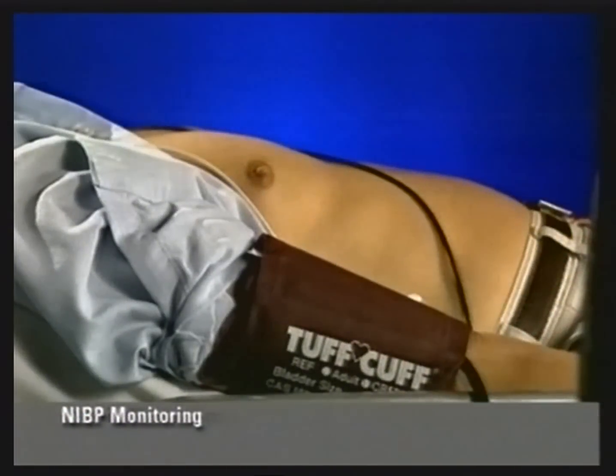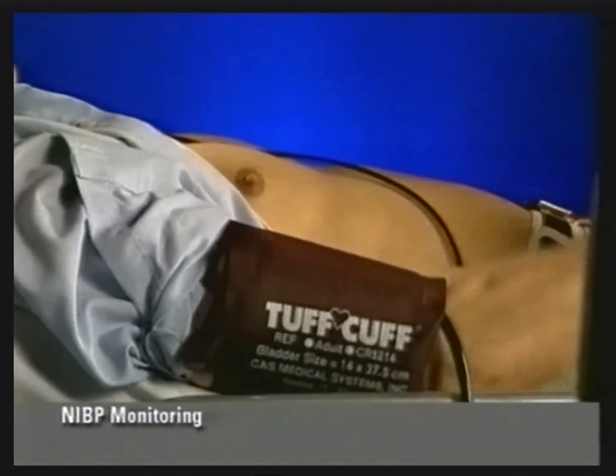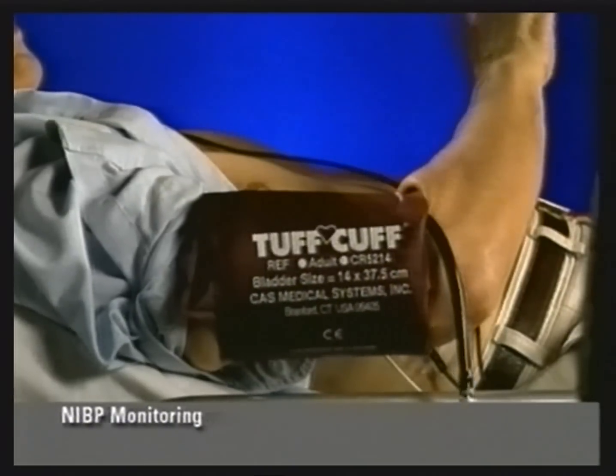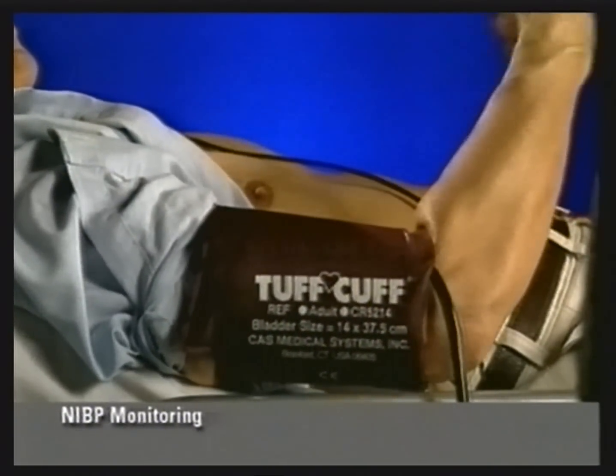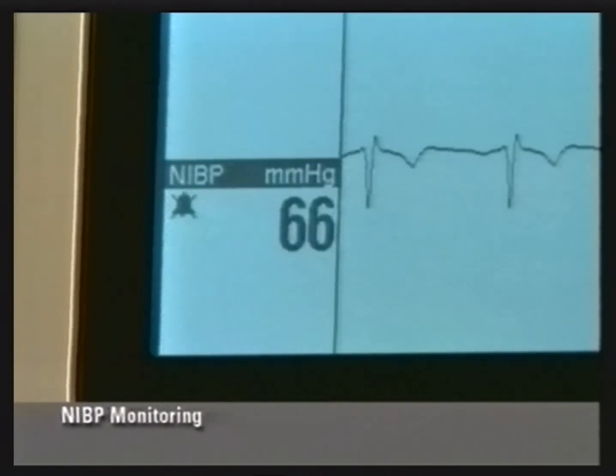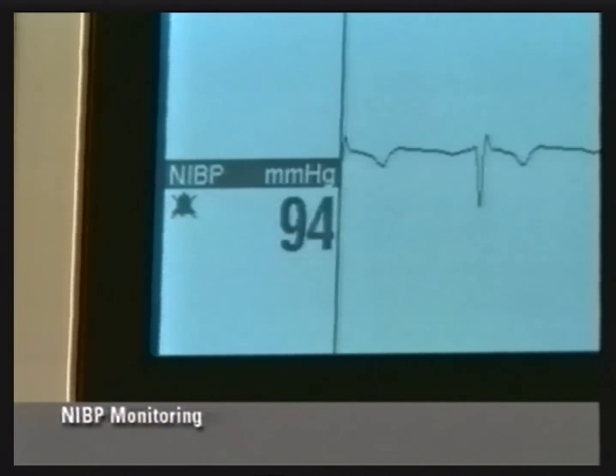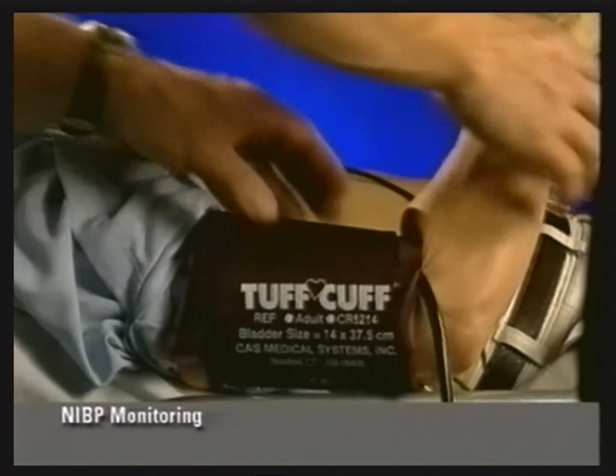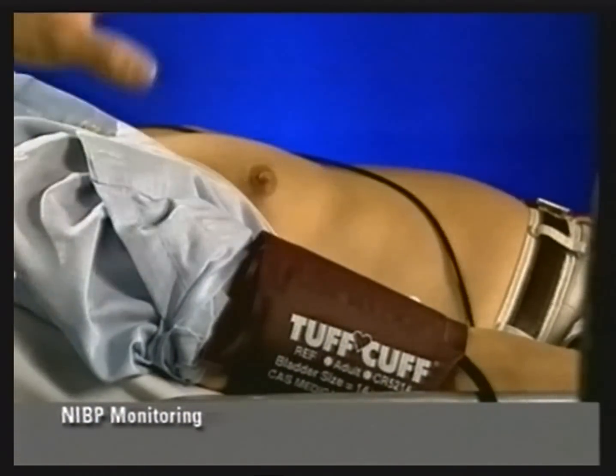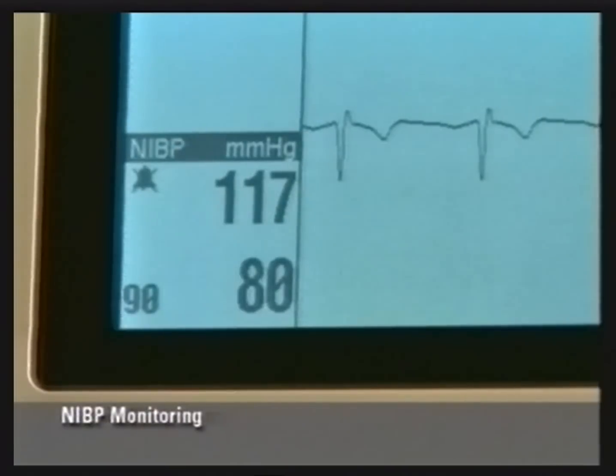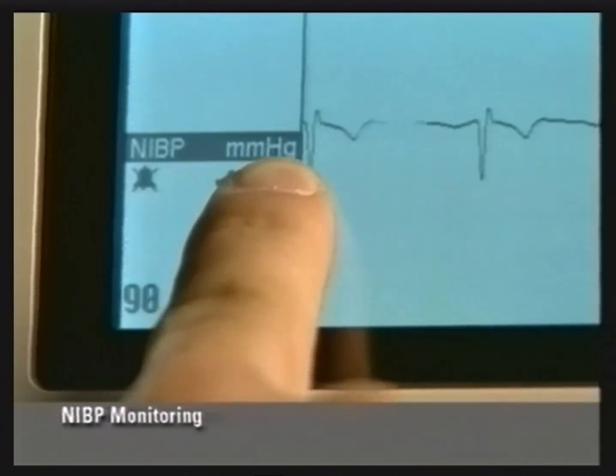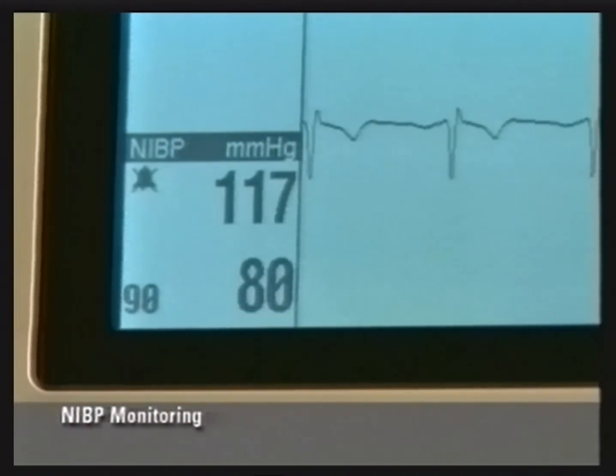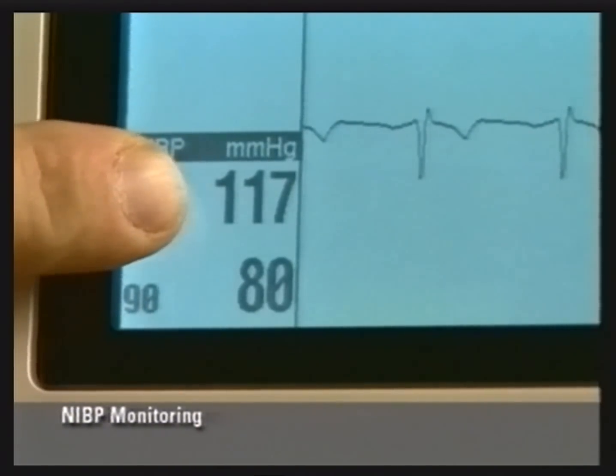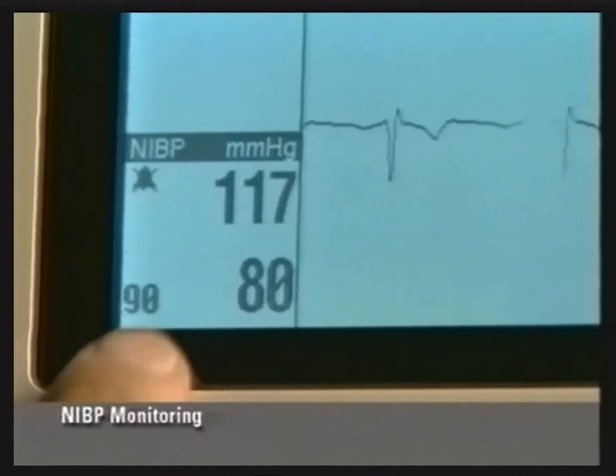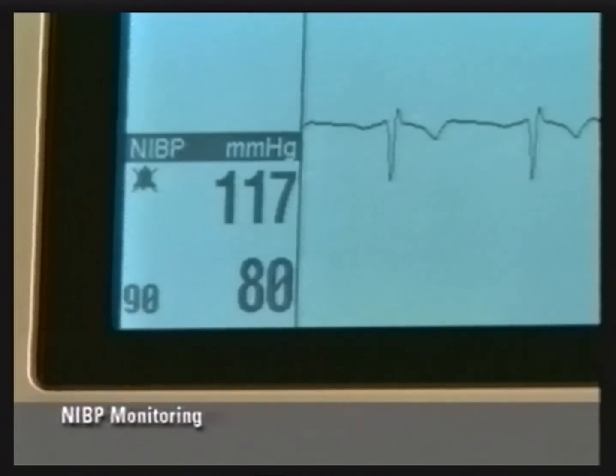Be sure the patient's arm is not moving during the deflation cycle. Arm movement will interfere with the measurement and cause the NIBP monitor to reinflate and take longer to obtain a reading. This can become very uncomfortable for the patient. The blood pressure is shown here in millimeters of mercury. Blood pressure may also be configured for measurement in kilopascals. The top number is the systolic pressure, the bottom number is the diastolic pressure, and the smaller number to the left is the mean pressure.